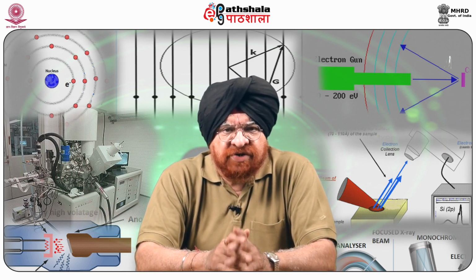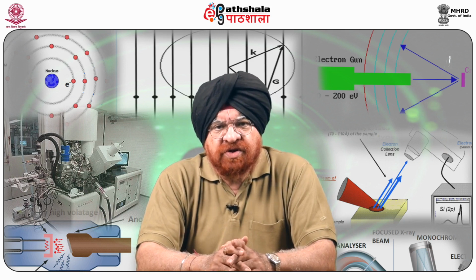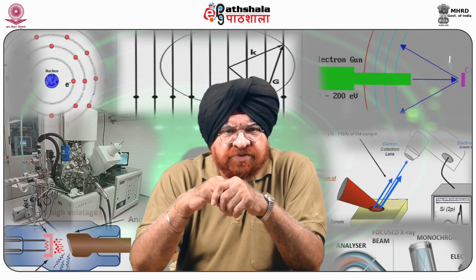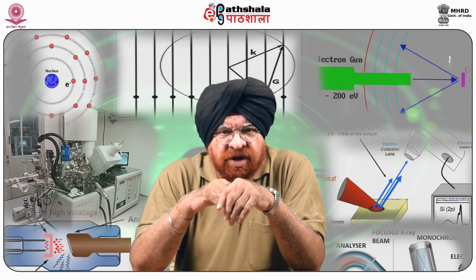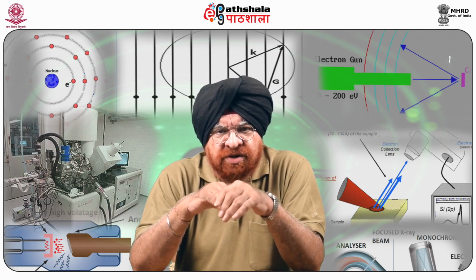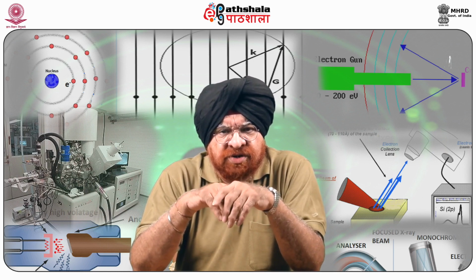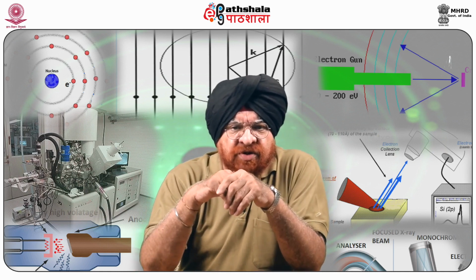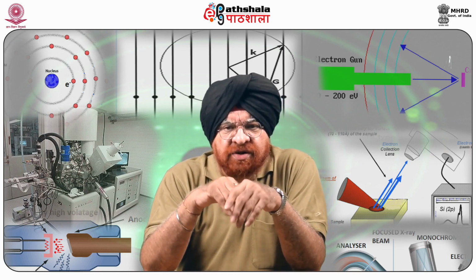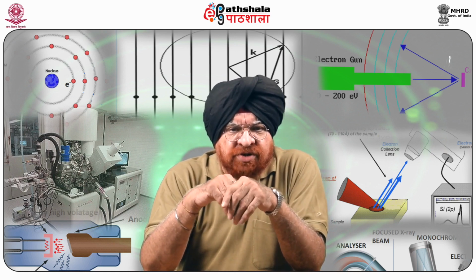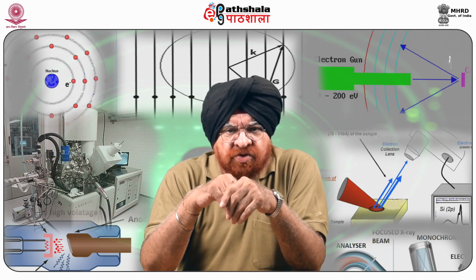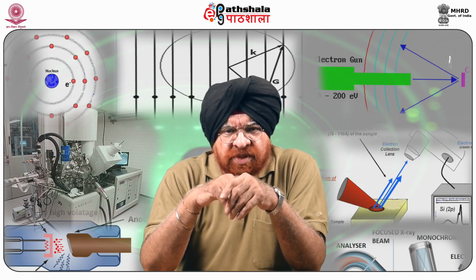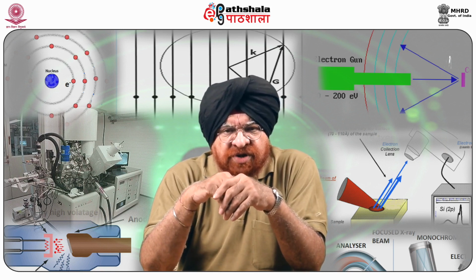First is sector field. It works as a combination of a magnetic analyzer and an electrostatic analyzer. The electrostatic analyzer selects the kinetic energy of the ions, and the magnetic analyzer selects the mass to charge ratio accordingly. The degree of deflection of ions by the magnetic field depends on the mass to charge ratio. Its high extraction energy, as we call it, results in surface roughness and charging.